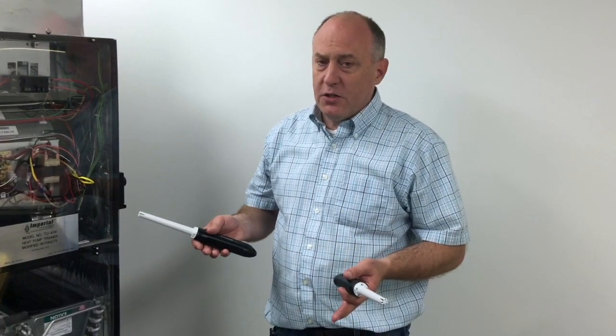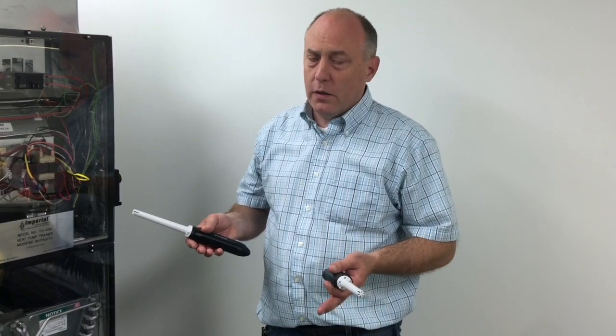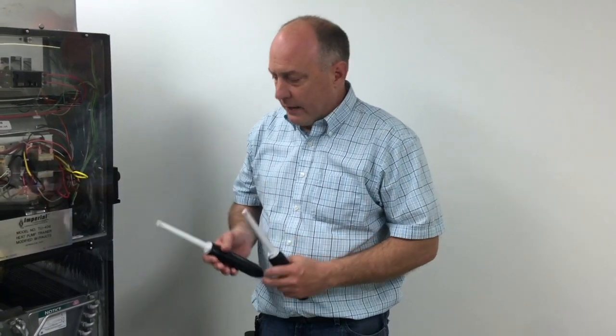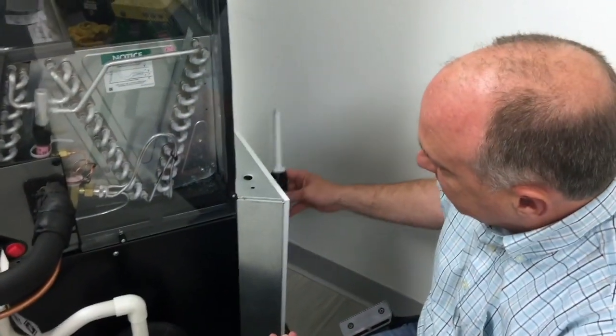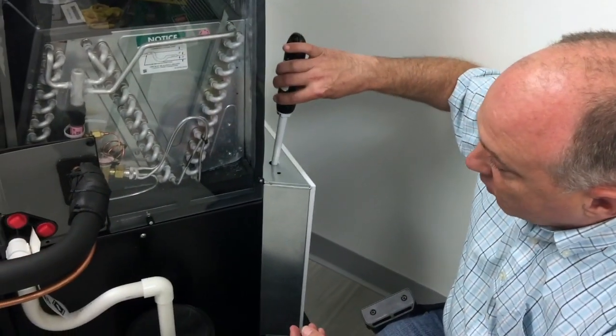This is the same if you're going to measure temperature split across any evaporator coil. You don't want to be right in line inside the coil. So again, you can see if we're going to measure, we should be on the side of the filter rack or in this hole here.